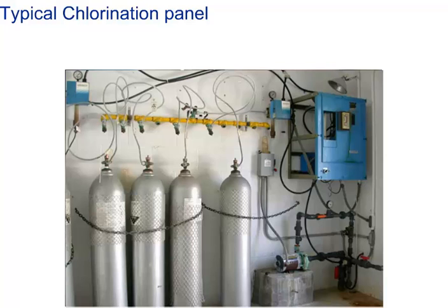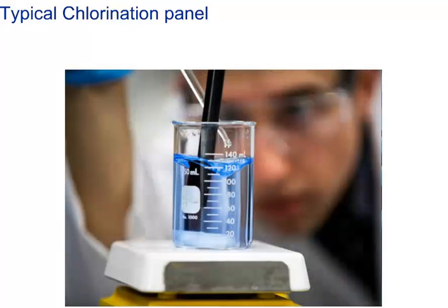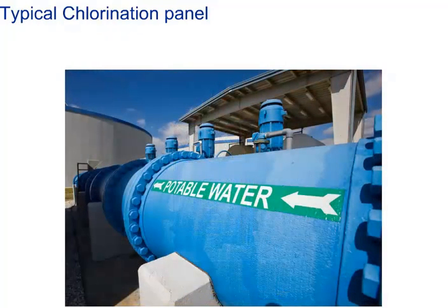The final process before storage or distribution is disinfection. This step is used to kill pathogens that pass filters and also improves taste and odor. Typical methods employed are chlorine. Chlorination is the most economical and commonly used: chlorine gas, sodium hypochlorite, bleach. Chlorine dioxide, chloramines, ozone: most efficient but expensive. Irradiation with ultraviolet light, which is very efficient. Other methods that you may find are sonification, electric current, and gamma-ray irradiation. From here it is off to storage or distribution to customers.